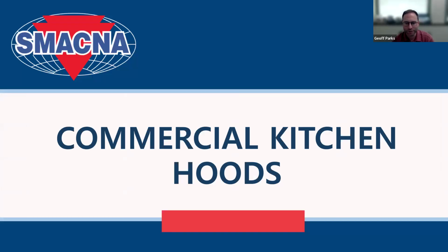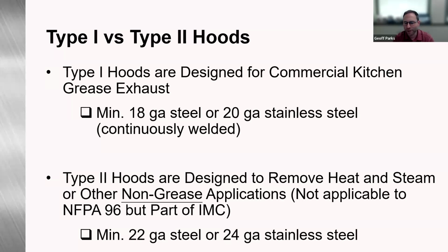So, commercial kitchen hoods, type 1 versus type 2 hoods. Well, type 1 hoods are designed for commercial kitchen grease exhaust, minimum 18 gauge steel or 20 gauge stainless steel construction, all continuously welded. Type 2 hoods are designed to remove heat and steam and other non-grease applications. So whenever there's grease involved, you need to go to a type 1 hood. No grease, just heat and steam, that's where a type 2 hood can be used. And this minimum construction is going to be 22 gauge steel or 24 gauge stainless steel.